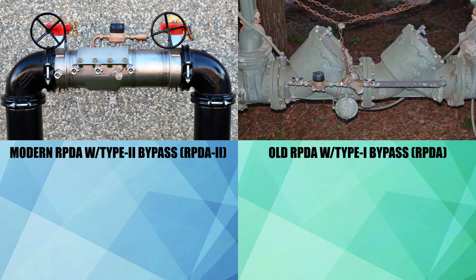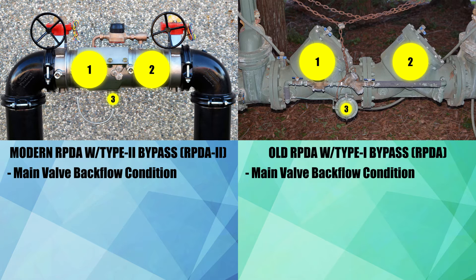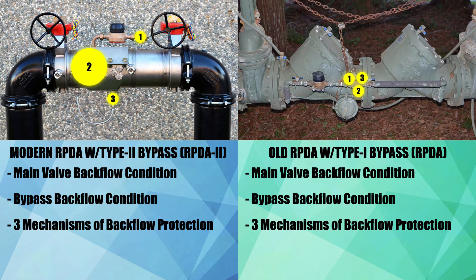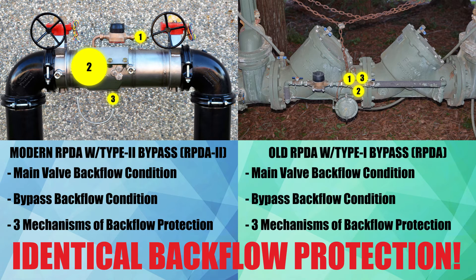Both the modern RPDA Type 2 and the old RPDA Type 1 protect both the main valve and the bypass flow paths with two check valves and a relief valve, providing identical protection to your potable water system.